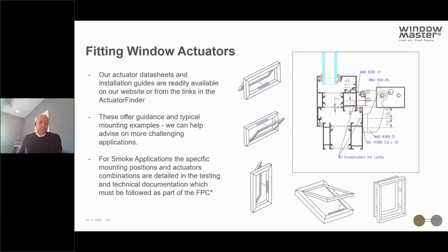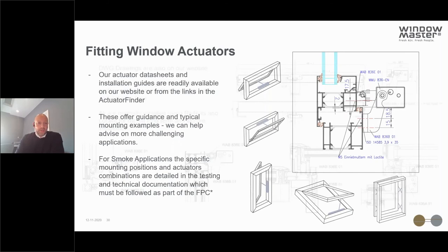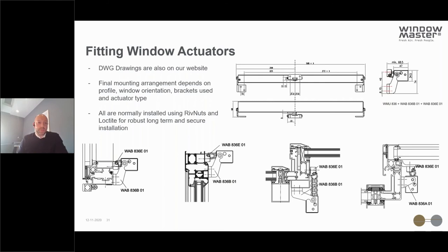Our data sheets and installation guides are a really good resource for working out actuator fitting, with links to these within the actuator finder output. They offer typical mounting examples for most window orientations and profiles, and our in-house team can help on specific applications. For smoke applications it's much more rigid — actuators need to follow tested arrangements and use components approved as part of the testing and technical documentation, which is followed as part of factory production control for smoke vents.